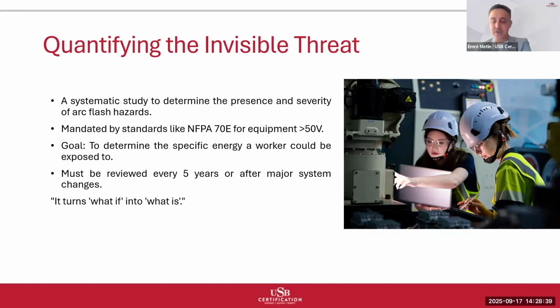But here's what makes this particularly complex. Arc behavior doesn't follow simple linear relationships. Small changes in the system configuration can create large changes in incident energy. This is why the analysis requires specialized software and expertise. The key output is converting what-if scenarios into what-is realities. Instead of wondering what might happen if there is an arc flash in the main electrical room, you get specific answers. An arc flash at panel MDP1 will create 18.5 cal/cm² at 18 inches working distance with an arc flash boundary of 8 feet. This specificity is what enables informed protection decisions.